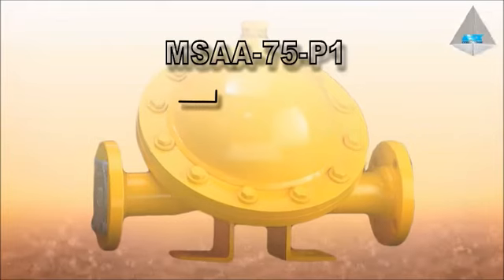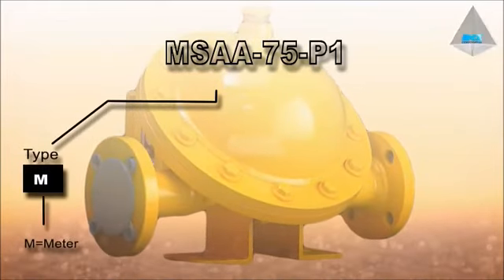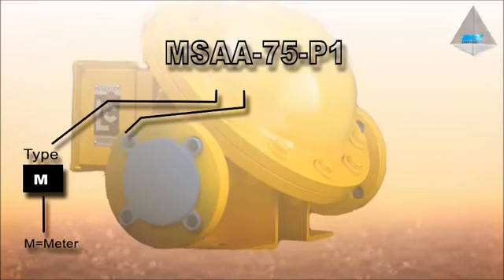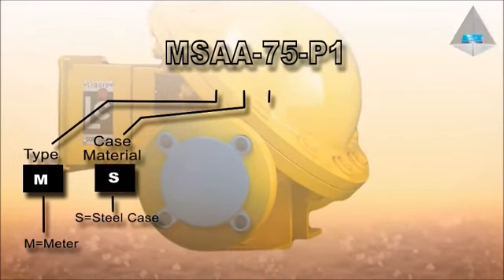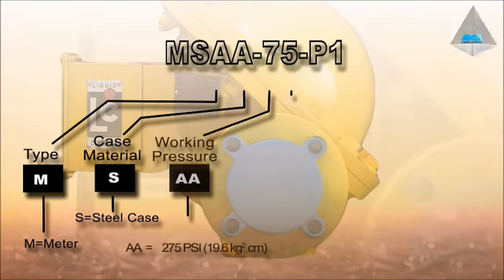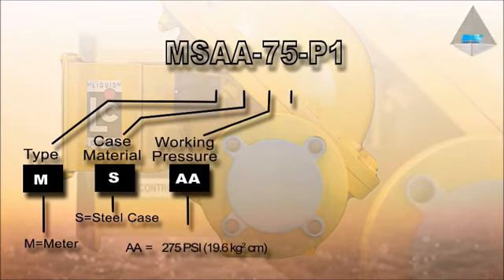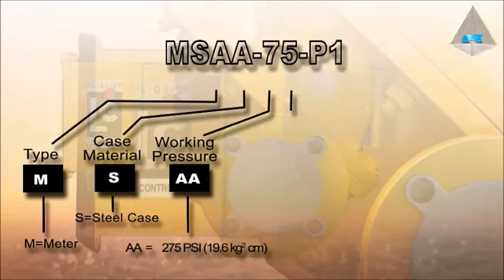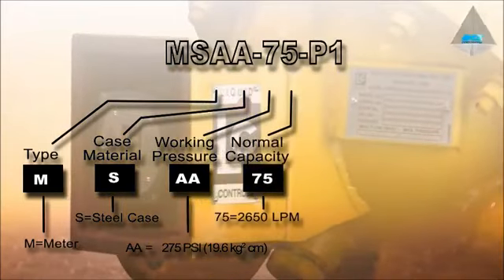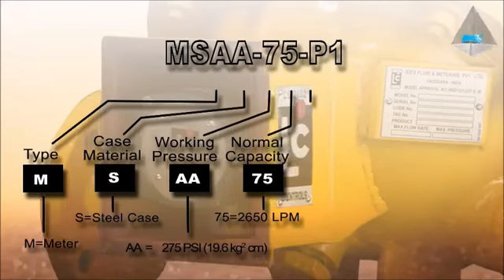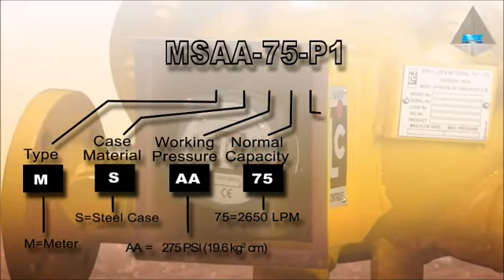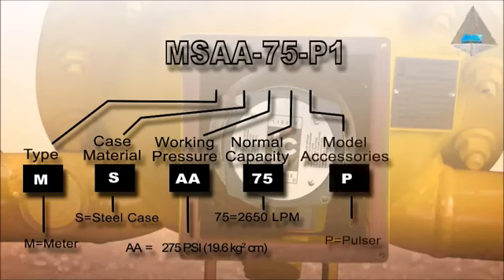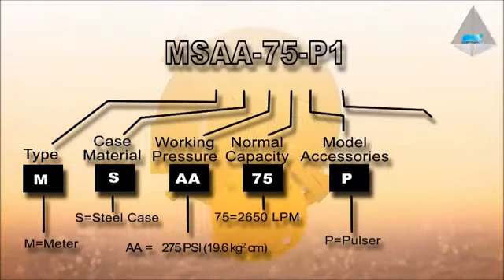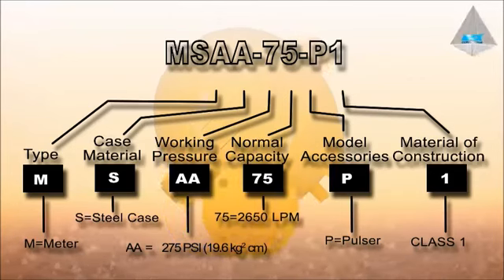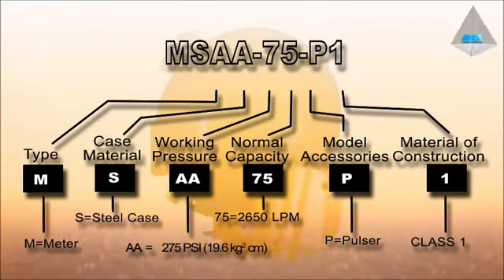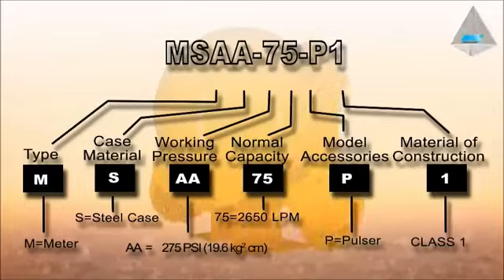MSAA 75P1, where M stands for meter. S represents the steel case design. And AA is the nomenclature for the pressure rating of 275 psi. 75 means a 4-inch size flow meter having a flow range up to 2650 liters per minute. P shows the accessory pulser mounted on the meter. And 1 is the meter class indicating the material of construction of its internals.